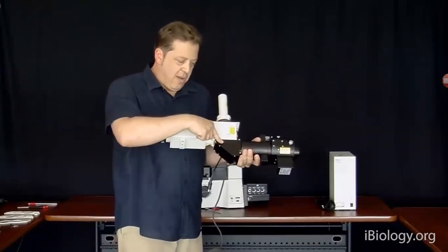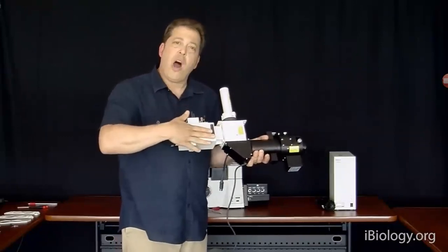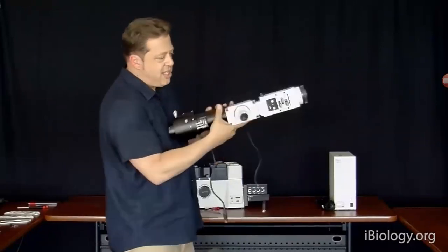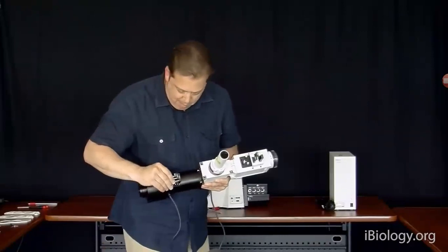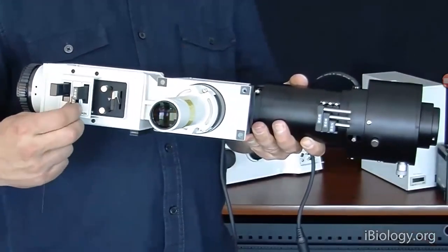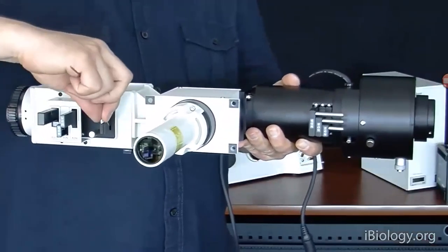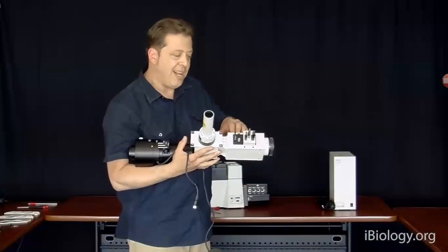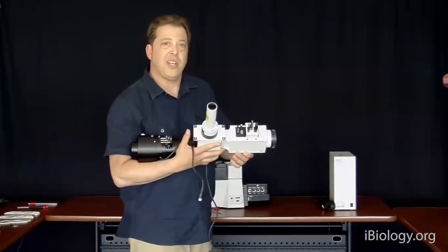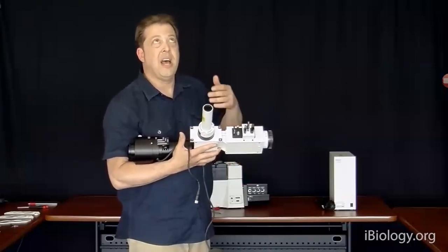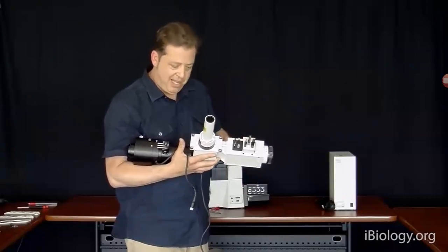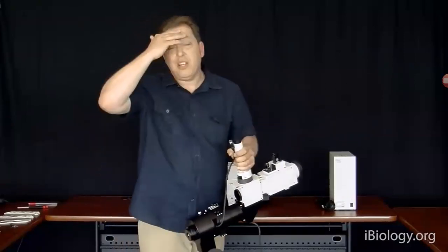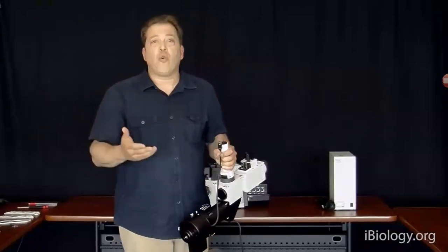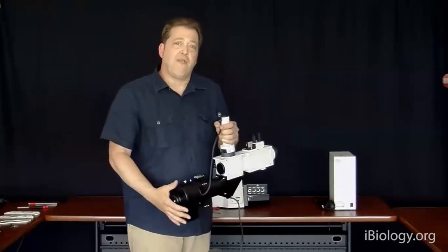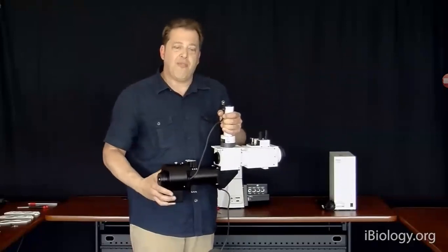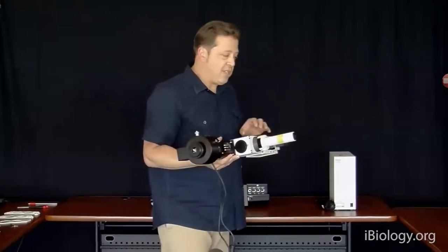There's an optical merge system here. There's a mirror here and then a motorized mirror here, and standard wide field epifluorescence through the other side. And you can see here on both sides, we've got multiple neutral density filters, as well as an aperture diaphragm on the epifluorescent side. The aperture diaphragm in the case of epifluorescence won't actually change the resolution of the system, but will act more like a neutral density filter and attenuate light, allowing you to decrease the amount of light on the specimen. In the case of fluorescence, the molecules within the specimen are actually your source of light. So you're not getting an image based on diffraction, but detecting the fluorescence that's being emitted from the specimen. So that's the epi illumination on the microscope.